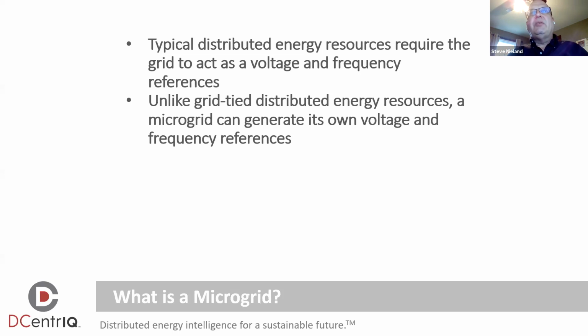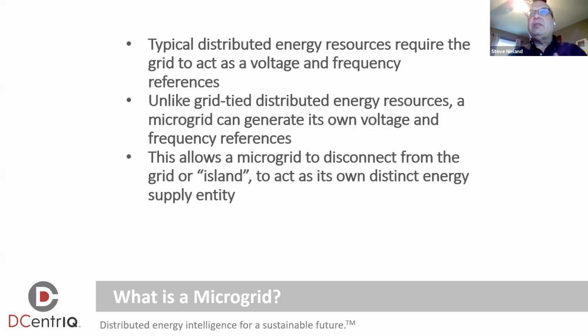So for a microgrid, those distributed energy resources can generate their own voltage and frequency reference, basically taking the place of what the grid would be supplying to that installation. This is what allows the microgrid to disconnect from the main grid, or island, acting as its own distinct energy supply.